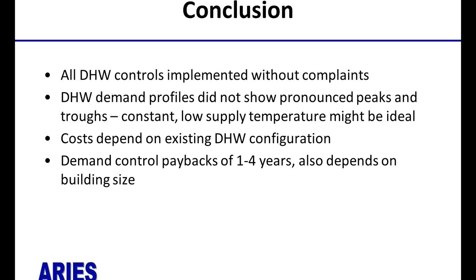Also, as I said, the draw profiles, the demand profiles, didn't show the pronounced peaks and troughs of on-peak and off-peak usage, and that may indicate that a constant lower temperature would be ideal in place of a temperature modulation strategy. The cost depended on the existing configuration of the building, but even then the paybacks for demand control were favorable. And again, this scales with building size and also fuel type. These buildings were using natural gas. More expensive fuels would make the payback more favorable.